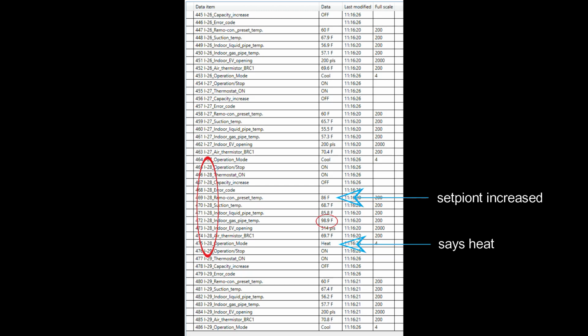This indicates that when this unit calls for heat, the port at the box opens and sends hot gas to this unit. We can check this unit off our list as a correctly wired indoor unit. But let's say hypothetically that we did not see hot gas going to this indoor unit. Or let's say there was something else wrong with this unit. Maybe the EEV was malfunctioning or the fan wasn't operating, whatever the scenario, you name it.